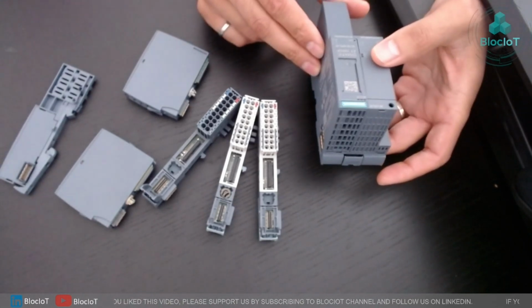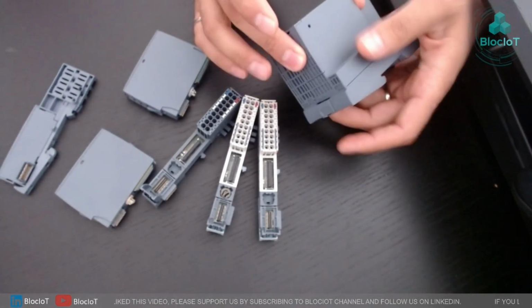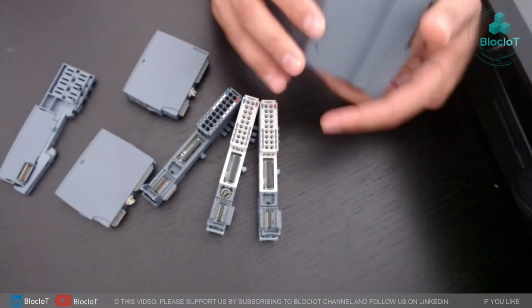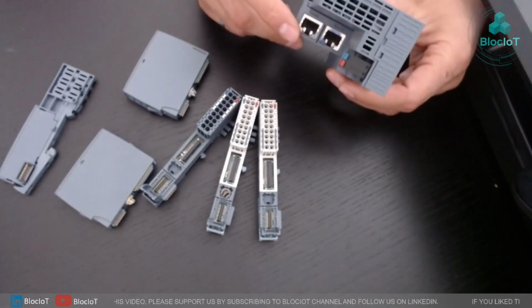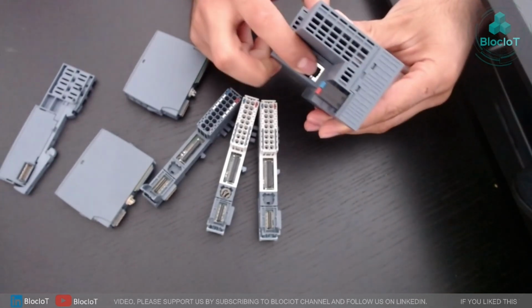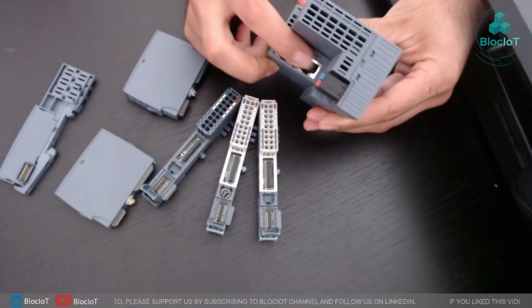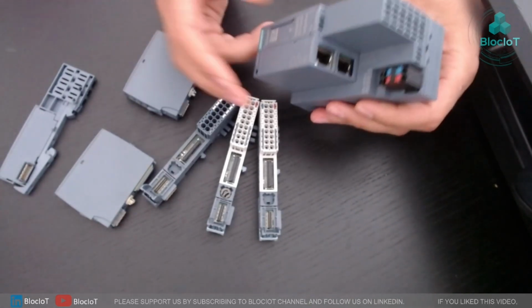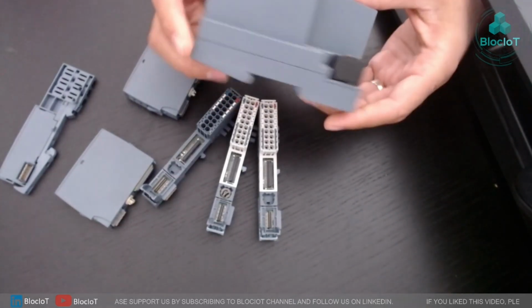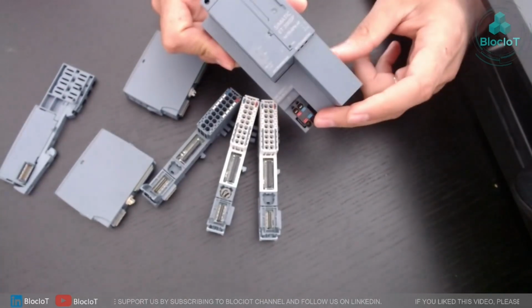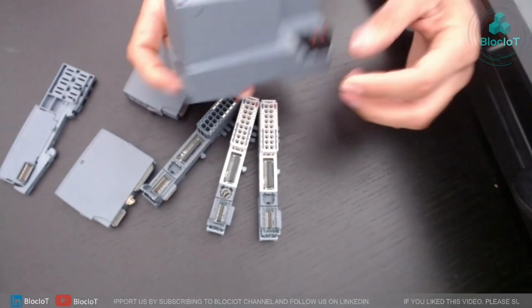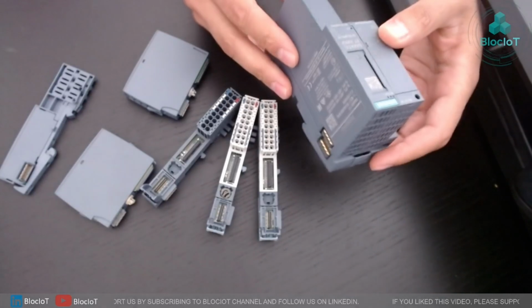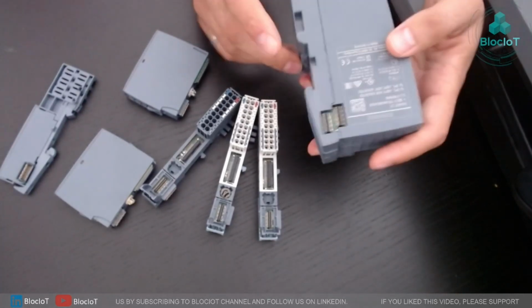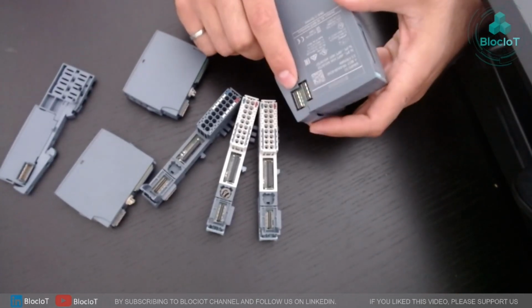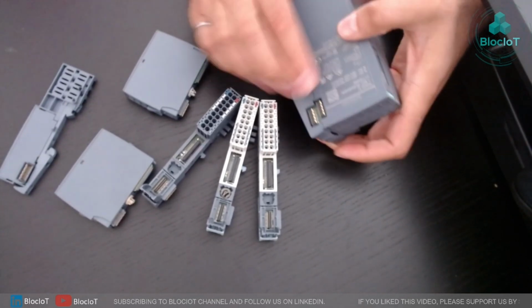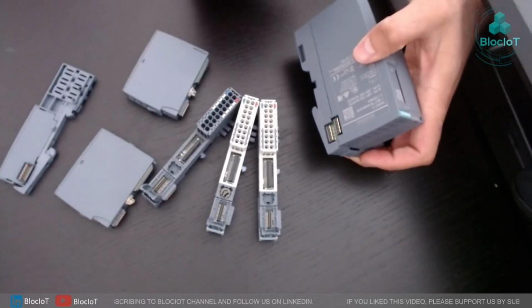It also has another component attached to the interface module called a bus adapter. Basically, the bus adapter gives you the capability to connect to PROFINET, EtherNet/IP, or even Modbus TCP networks. And as you can see here, there is a power adapter that you can connect your 24 volt DC to. And on the right side, you will see these connectors, which connect to the next module, which I'm going to show you next.